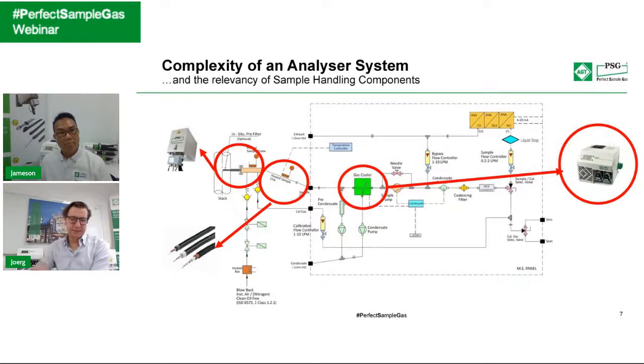So what we are looking at here, in most of the cases, is IR, infrared, or UV analyzer technology. What would you say in your region, Jameson? Maybe for emission monitoring, the most common analyzer types? Is that something you would confirm? Still the IR, the cold dry system. So mainly they are still using the IR more than any UV. So IR still, I would say, 90% of the analyzers are IR. Wow. Okay.